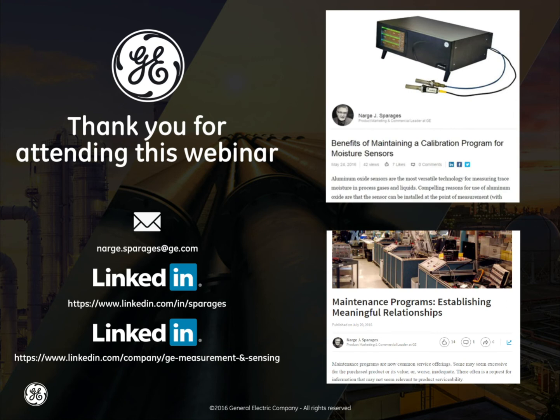The way that the GE aluminum oxide sensors are calibrated is that they're exposed to various levels of moisture, and we're recording the output of the sensor at those levels of moisture. So in essence, what we're doing is we're characterizing the response of the sensor. So at, let's say, minus 50 degrees C test point, we're waiting for the sensor to come into equilibrium at minus 50 degrees C. We're recording the raw value, the raw signal from that sensor, and that's what actually gets on to the calibration data sheet or programmed into the sensor electronics.